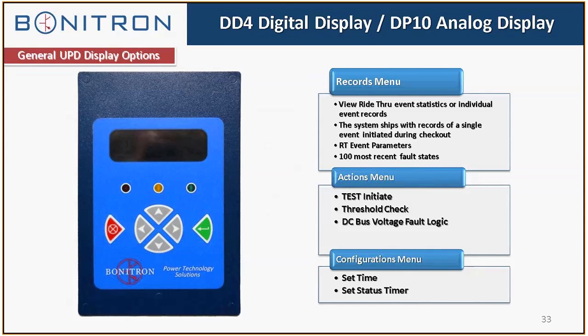This says 100 most recent fault states. Actually, it's 30. That's a typo. In the actions menu, there is a test initiate, and the ride-through test can be done online because what it does is raise the DC bus above the nominal level during the test. This isn't an actual ride-through event. You're actually raising up the level, and that's telling you if the test is successful that the ride-through is boosting. It will raise up the bus just high enough to test the ride-through, but not high enough to trip the drive on overvoltage. There's also a threshold check you can key into the display. All of these functions are outlined in the owner's manual for the DD4 display that's located on the website.